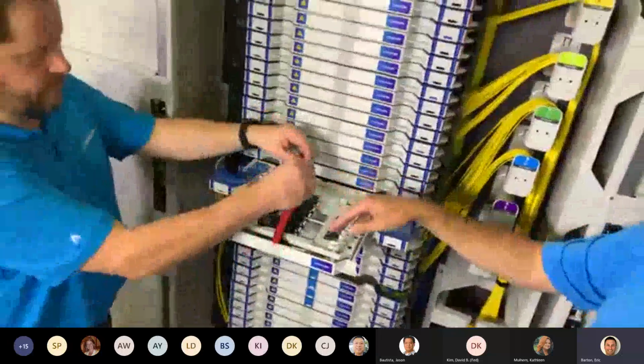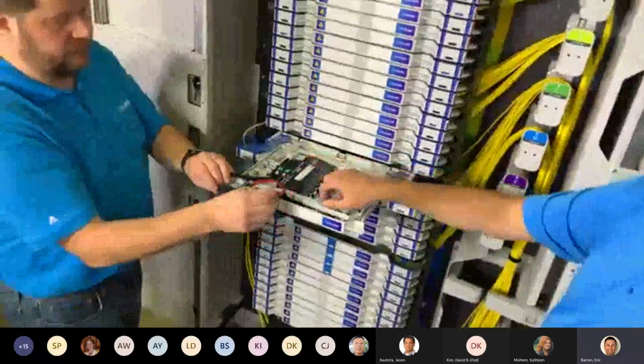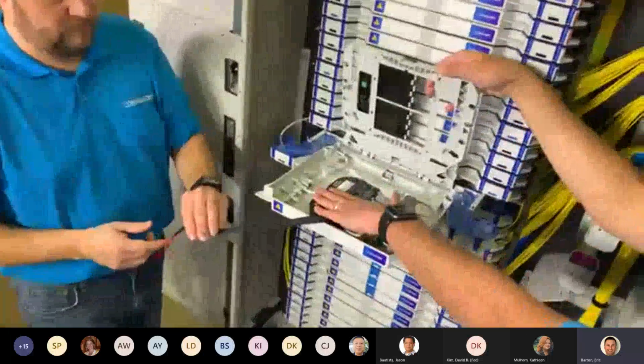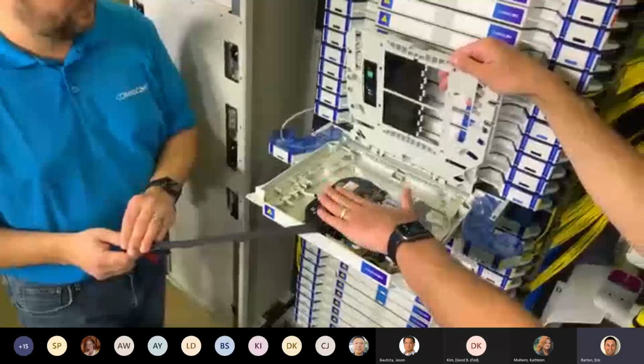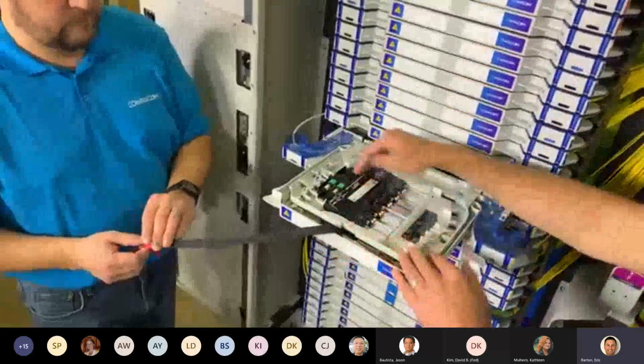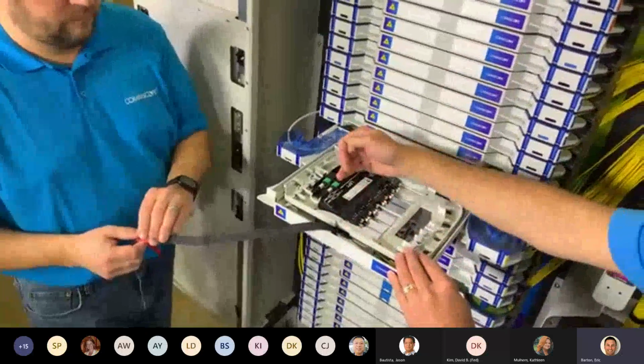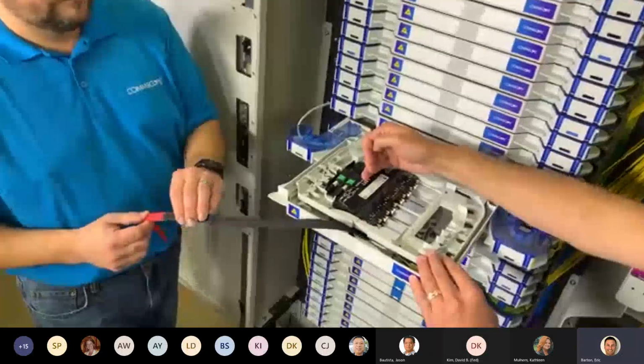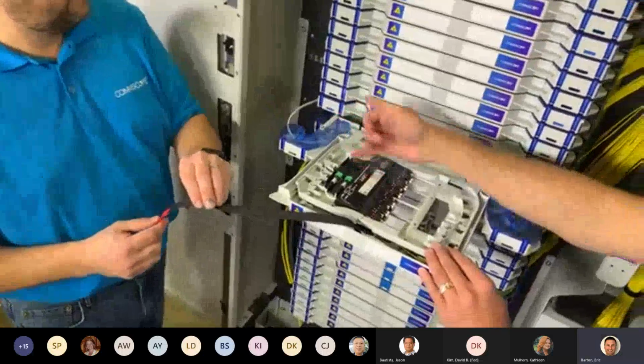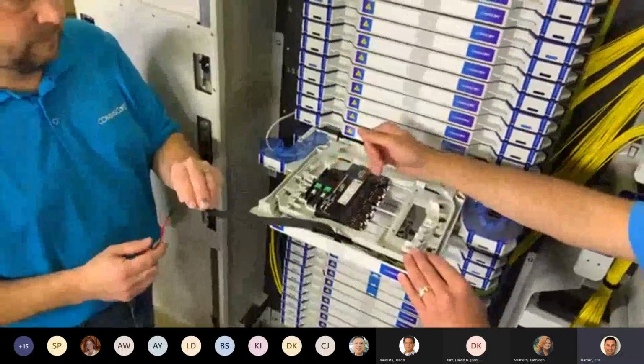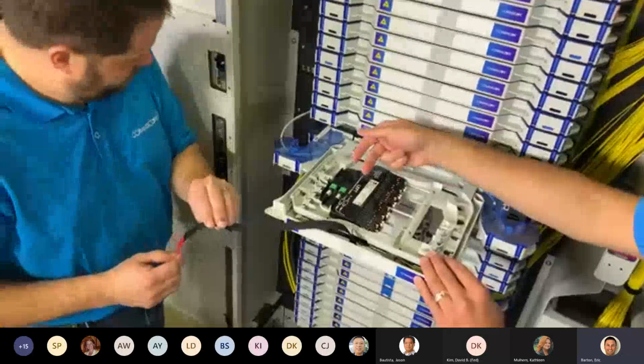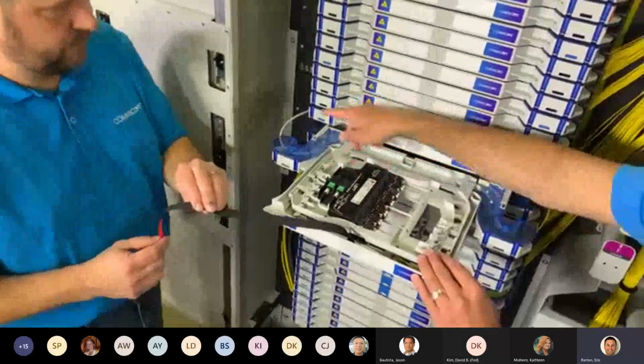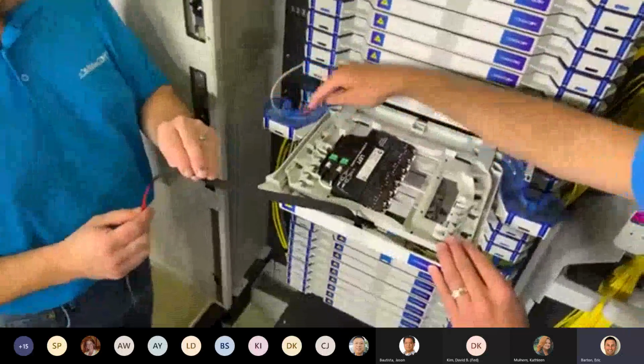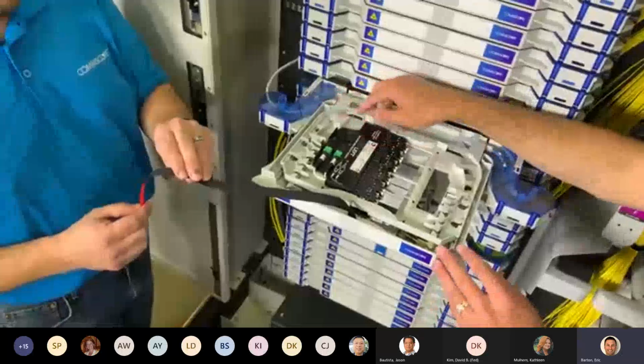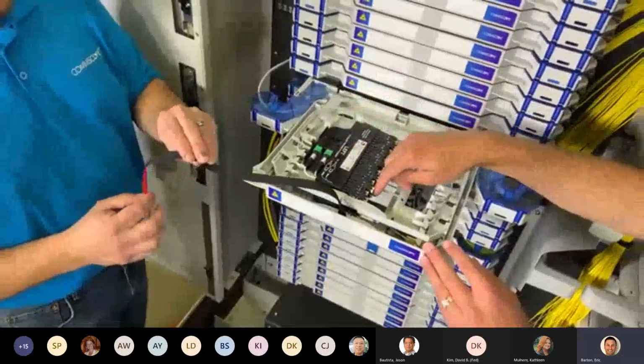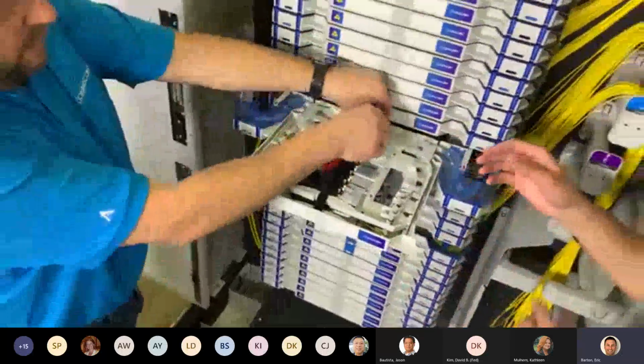So on the top here, these are 2 different inserts. As we said, this is a pre-terminated cable module that you're ordering by length. This one is an MPO to LC module. So if you were to order a 100-meter pre-terminated cable, this could be a 24 fiber pre-terminated MPO that breaks out into 2 12-fiber MPOs. You just bring your pre-terminated MPOs, without that CTU kit, into here, plug them in, and then use your patch cords.